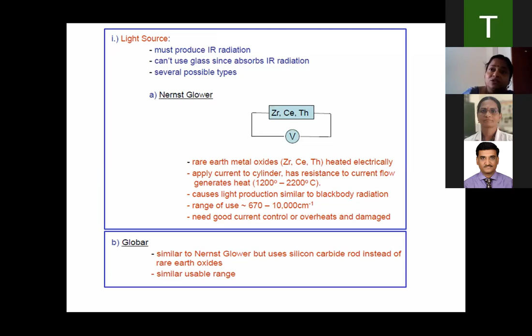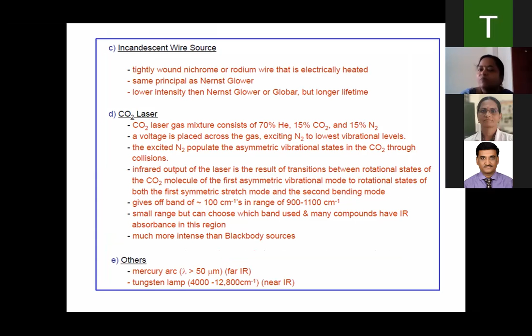What is the major application of these sources? These sources use different materials, and when the material is heated up, it has a tendency to produce IR radiation. Simple. So Nernst glower, globar source, incandescent wire source, CO2 laser. You can make a small tabular column. Nernst glower, yes, it comprises a material, rare earth metal oxides: Zr, Ce, Th. It should be heated up so that it produces the IR radiation. Globar source, silicon carbide. Then incandescent lamp, nichrome wire or rhodium wire, all this, right?